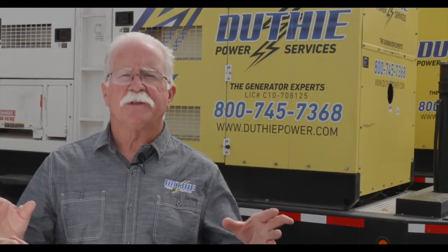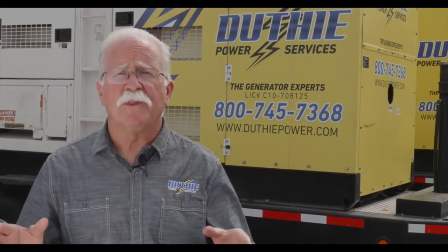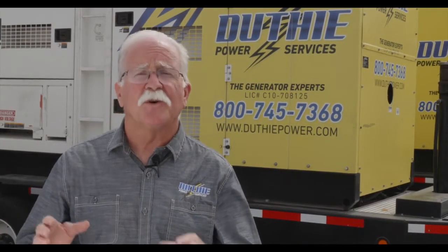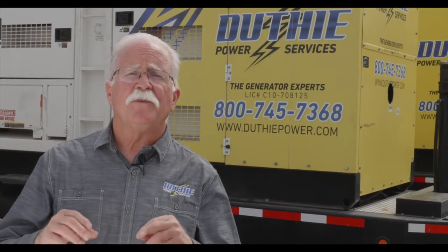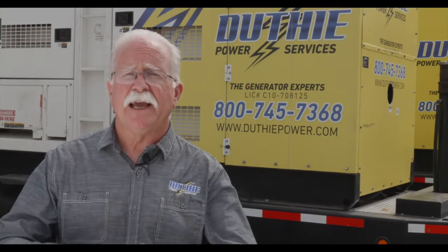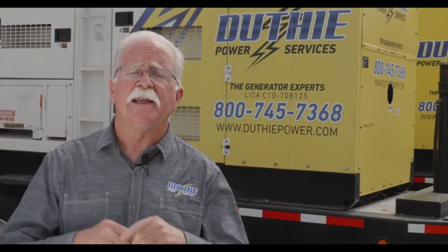When a generator has a fuel tank that is very large — we have one customer with an 8,000 gallon fuel tank — they're not going to consume that much fuel, so a lot of that fuel sits. On a more regular basis, generally suggested once a year, they should have that fuel polished to take out the water that can get in and the contaminants.